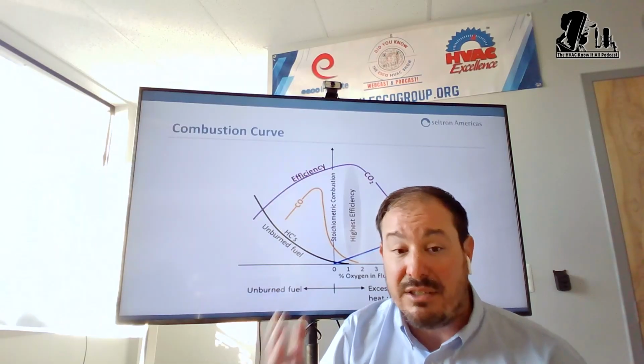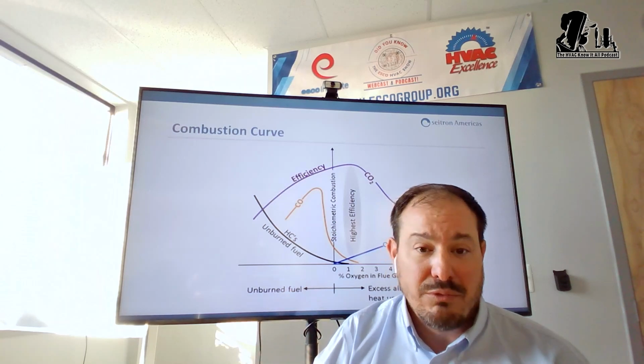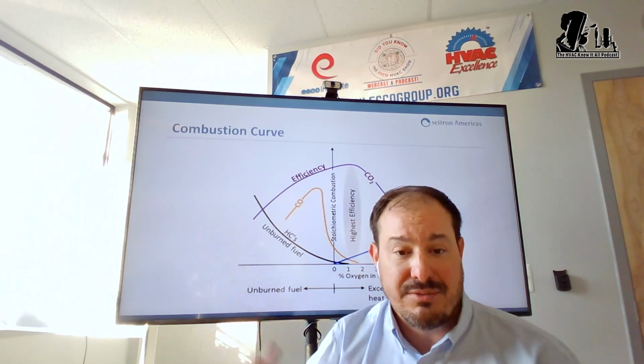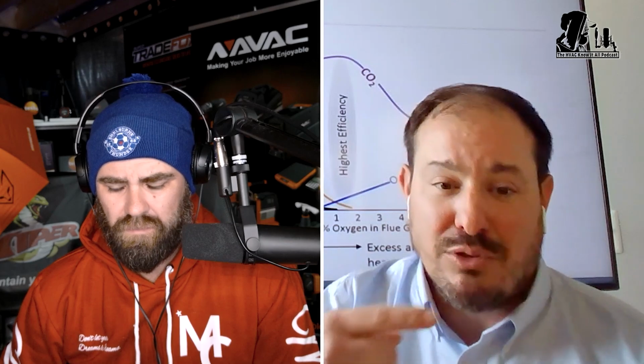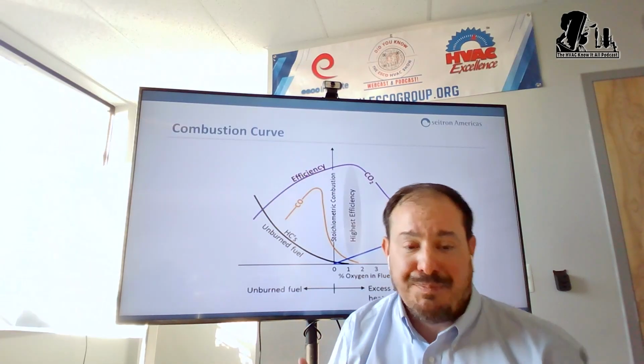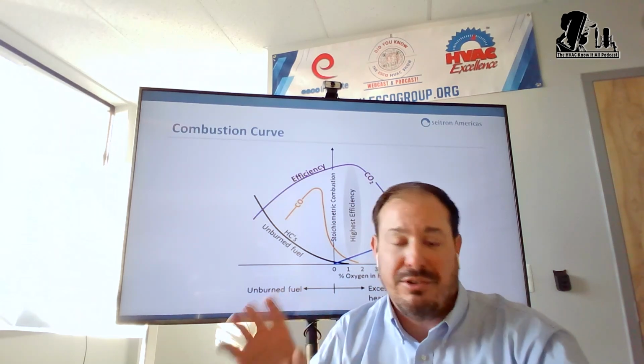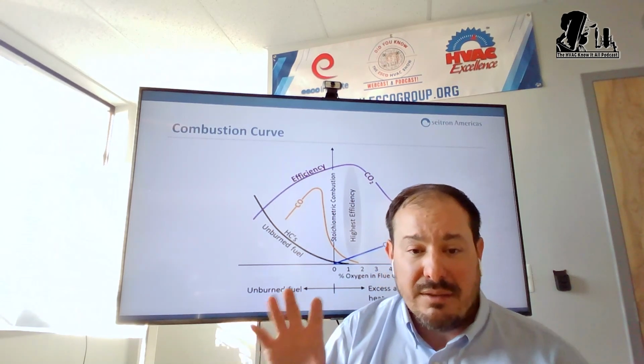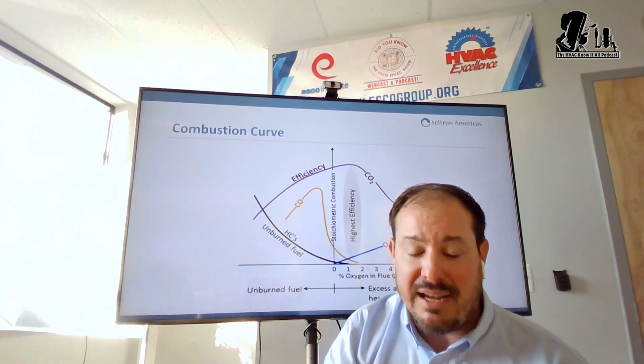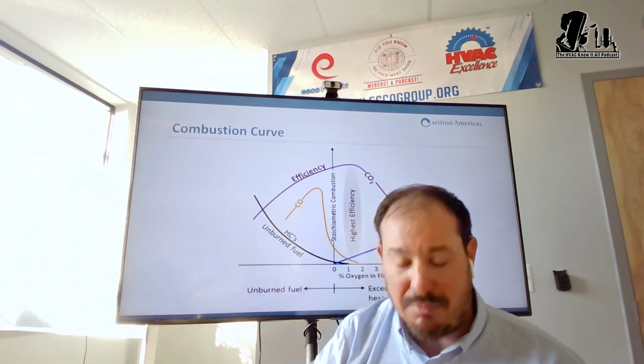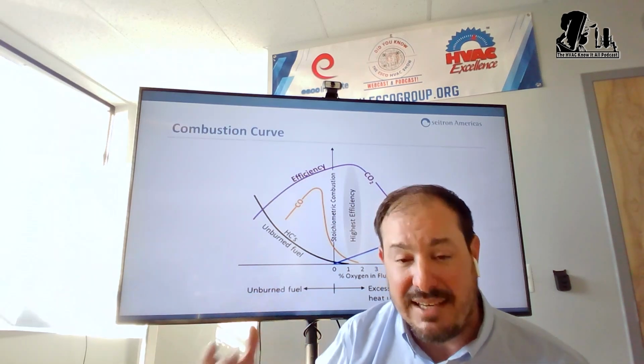Now, here's why it's a big deal in the HVAC market. Does anybody ever hear of what we call recirculation, crosstalk? You're venting materials, your O2, your CO, your CO2, the NOx that's in there too, when they all should be piped perfectly to get outside, right? Yes. But unfortunately, what we see is some recirculation, where sometimes those pipes aren't piped correctly outside, and we start pulling back in those byproducts from combustion. So you're kind of vented too close together. There are all different types of reasons why, but if you don't vent properly outside, instead of bringing clean air to the boiler, you might be bringing carbon monoxide, carbon dioxide, but also that acidic gas called NOx.